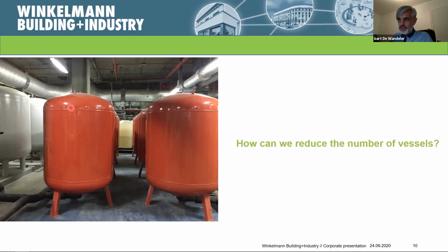Also because it is really difficult to maintain a perfect stabilization of your P0. Because this is not a science, it's quite easy. The vessel here can, for example, have a P0 of 2 bar, but this one can have a P0 of 0.9 bar. There will always be a small difference. And this will also mean that this vessel has the risk to get full of water and break. And this vessel, due to a little bit higher P0, will never work.